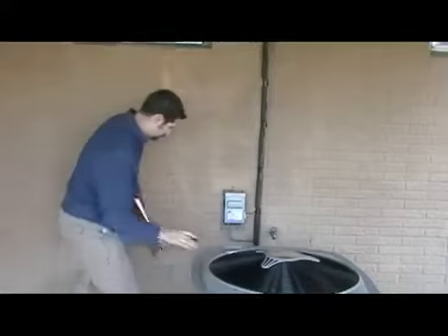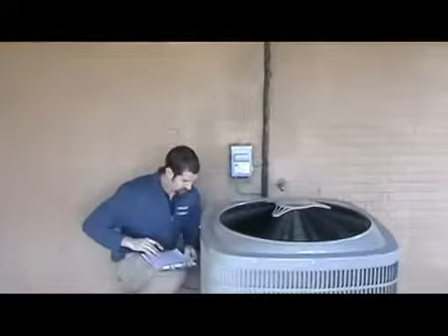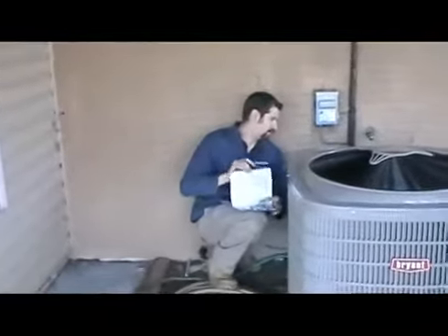Then we'll do a walk around the outside, just look for any areas that might be water and air infiltrating, get the efficiency of the AC units, efficiency of the hot water heater, potentially the furnace, make sure that it has good stack pressure, make sure that it's not spilling under the hood or anything, that the gases aren't spilling when it turns on. Inspect the attic, look for the insulation levels, look to see if there's open chases, as general areas where there might be air penetrating into the conditioned space.